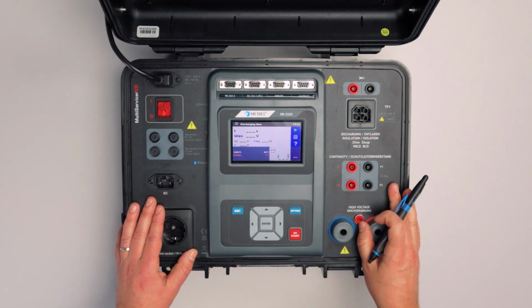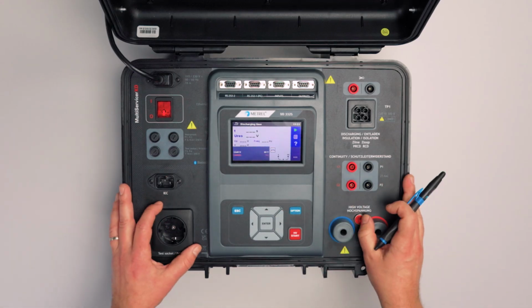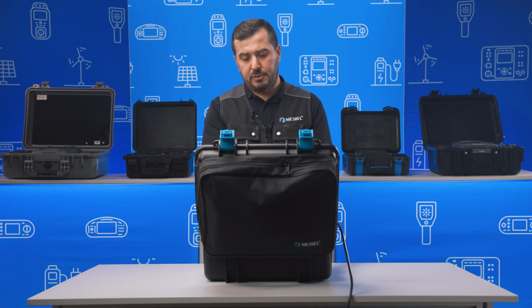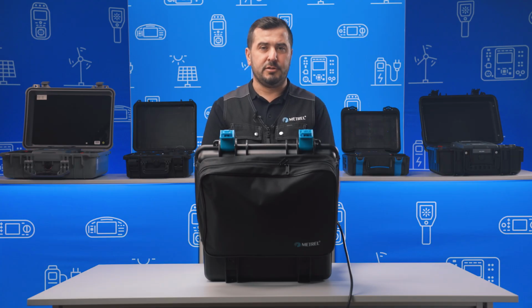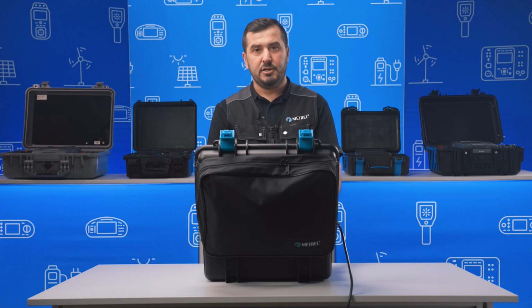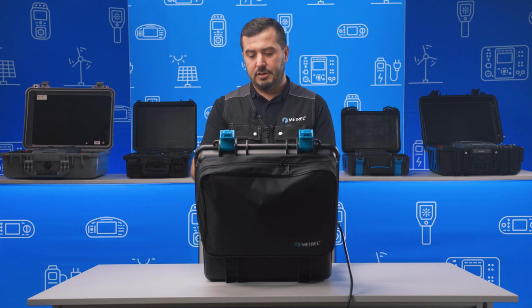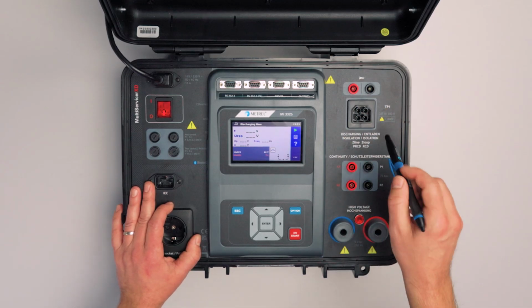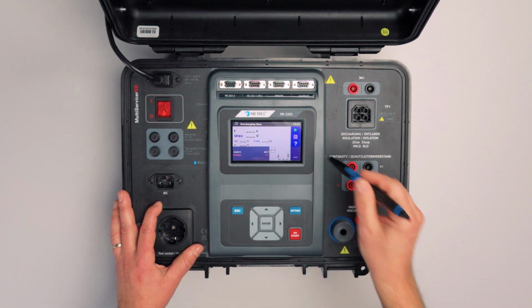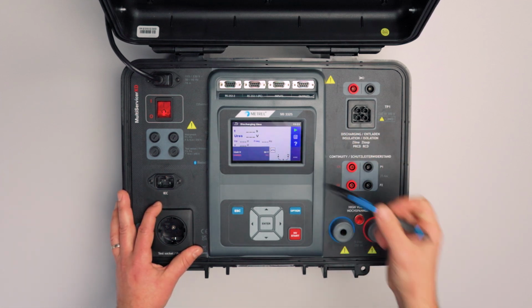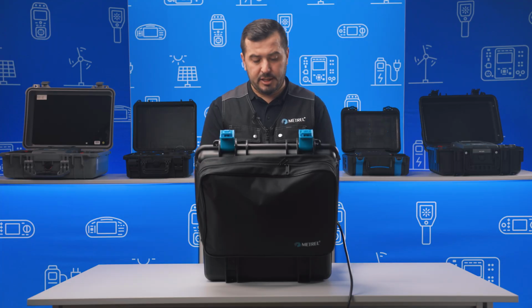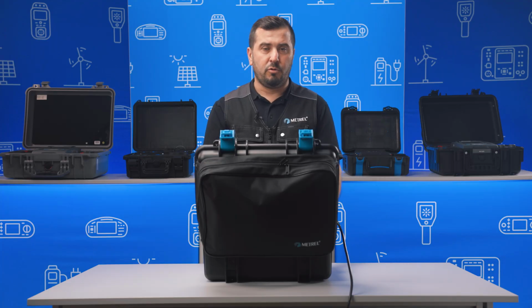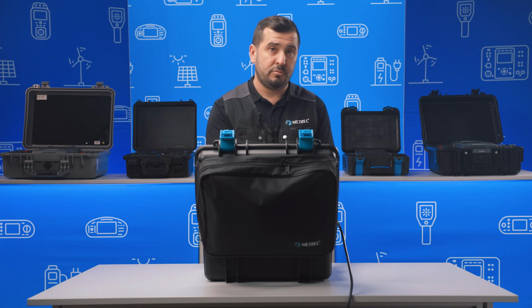Then discharging time, or the residual voltage measurement. For this particular measurement, as I mentioned early in the beginning of this presentation, it is important to use the brown cable which is dedicated for the residual voltage test. The measurement will return us the discharging time and the residual voltage of the tested appliance or machine.